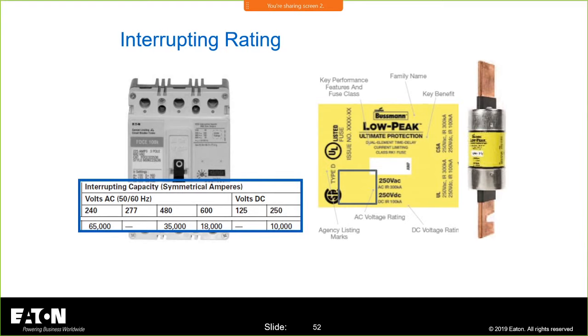Don't confuse short circuit current rating with interrupting rating. The short circuit current rating is the rating of the equipment. The interrupting rating is the ability of the overcurrent device to stop the flow of current.